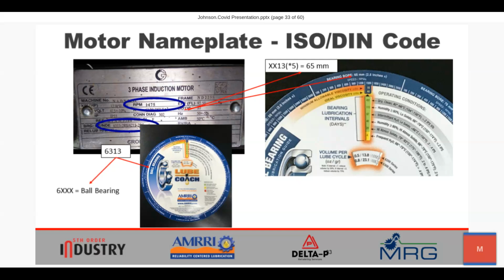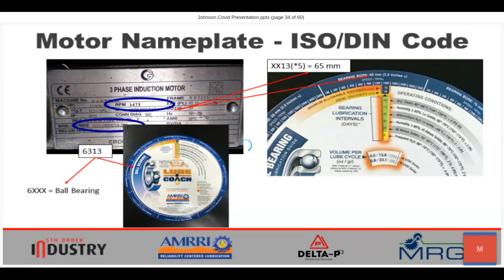In this instance, off of the nameplate, we see the 6313 bearing designation. 6, once again, represents ball bearing. 3 represents the gauge of the bearing. And 13 represents the value that, when multiplied by 5, gives us the bore dimension in millimeters. We turn to the 65 millimeter value on the calculator.